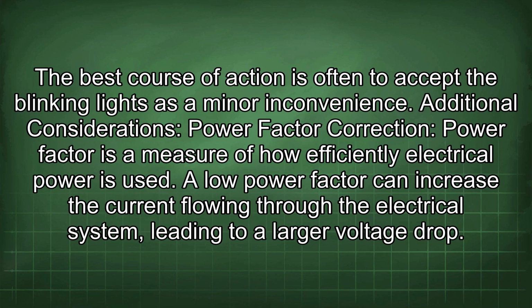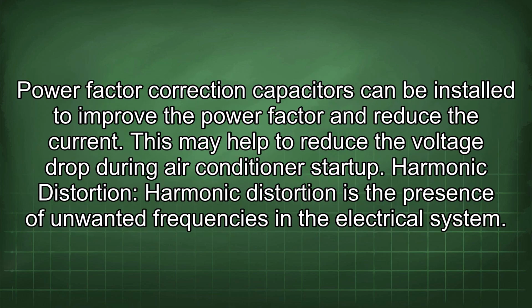Additional considerations. Power factor correction. Power factor is a measure of how efficiently electrical power is used. A low power factor can increase the current flowing through the electrical system, leading to a larger voltage drop. Power factor correction capacitors can be installed to improve the power factor and reduce the current. This may help to reduce the voltage drop during air conditioner startup.